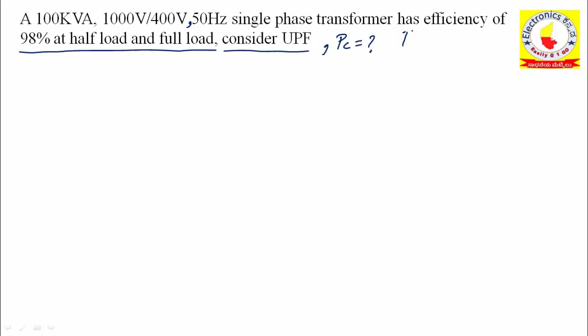So efficiency, what is the formula? X times of VA into cos phi, whole divided by X times of VA into cos phi plus PC plus X square times of PCU. This is the formula for efficiency.